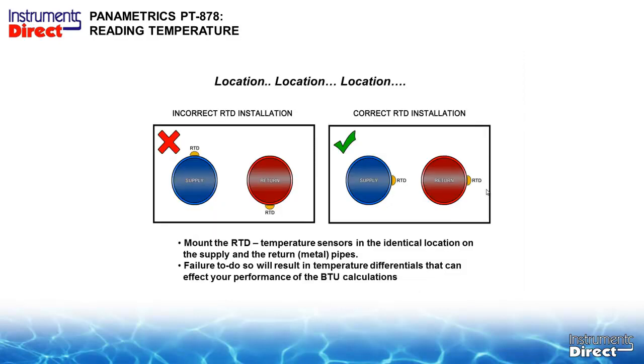Now, this is where people make another really big mistake. They say, well, it's BTU, let's throw it on the pipe and we've got good data. If you don't do it correctly, you can get bad data. If you're off 5% on the temperature, you can be off 25% on your BTU calculation. So what you really need to do is take note. You're looking for temperature differential. A clamp-on temperature sensor is not the exact temperature sensor, so we limit it to metal pipe applications.